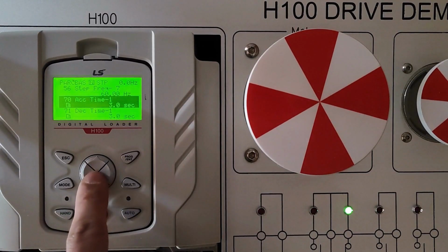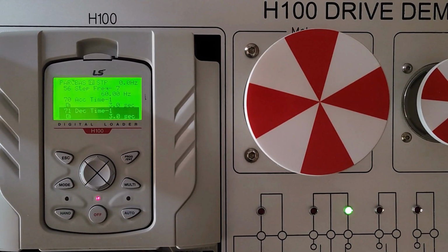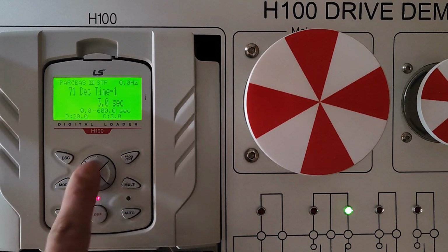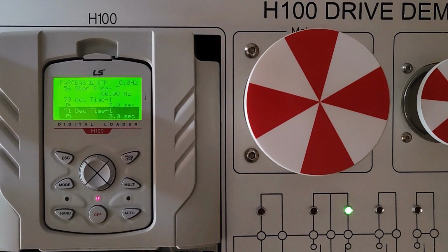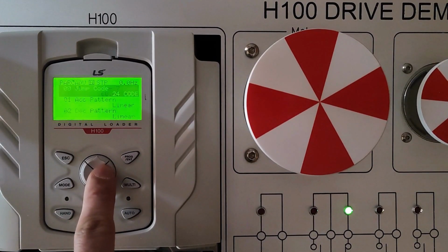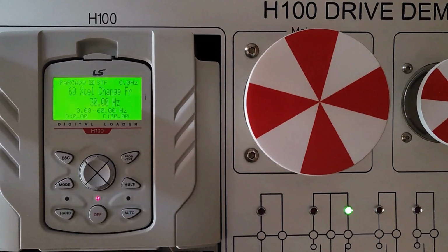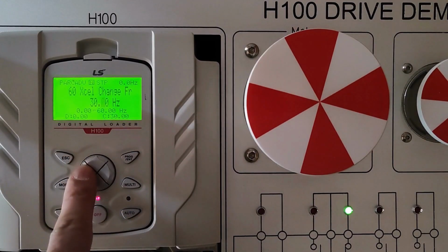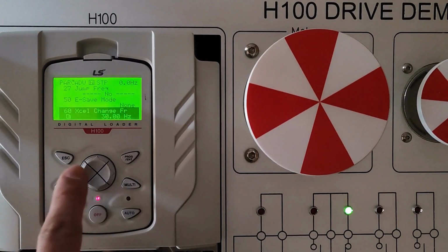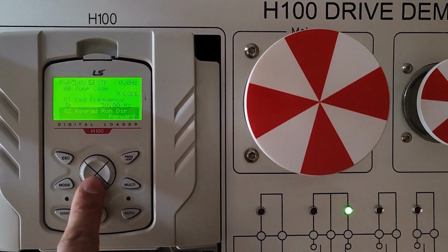In Base 71, it's the deceleration time. That was our second time, meaning from when it reaches a frequency of 30 Hz, from 30 Hz down to 0 Hz, in how many seconds it should do that. We said we'll also set that to 3, so we set it to 3 and confirm it. Our next parameter is the advanced setting, the frequency value before and after which the ACC and DEC will change. We said in this video we want to set it to 30, so we set it to 30 and confirm.